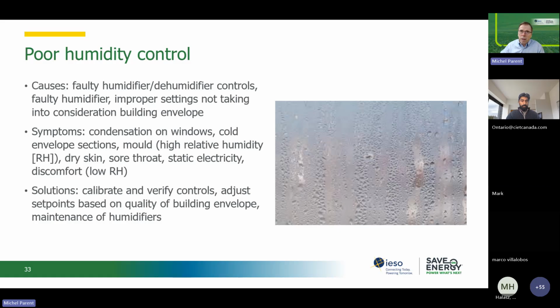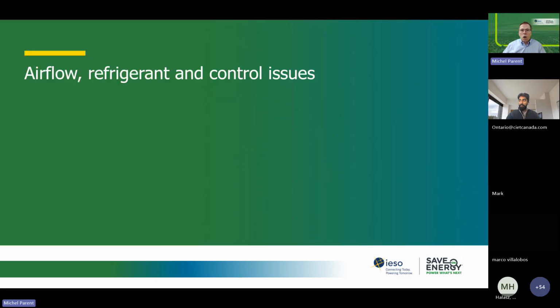Most commercial buildings, their humidifiers are no longer working because they're such a pain to maintain. But if you do have a working humidification system, those sensors are critical, because if you provide too much humidity, again, it's a health concern, because too much humidity means potential for mold growth. So it needs to be part of what we call the critical sensor calibration plan, which should be part of your PM program for the BAS.